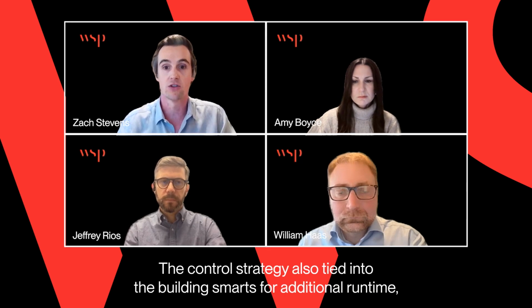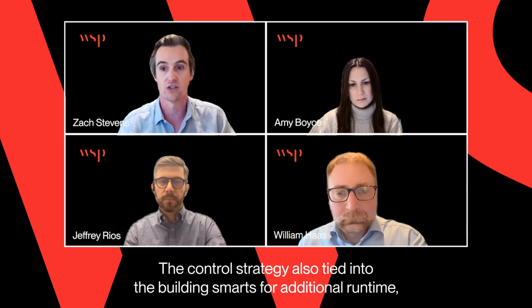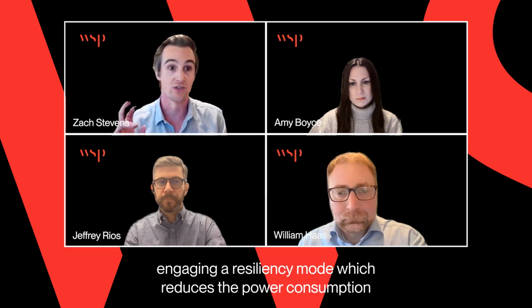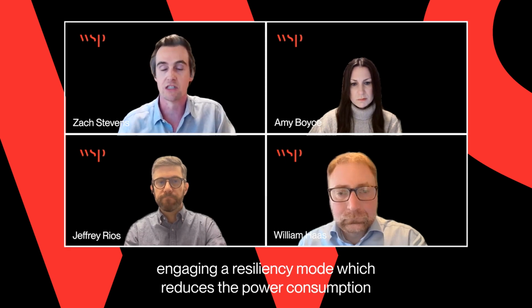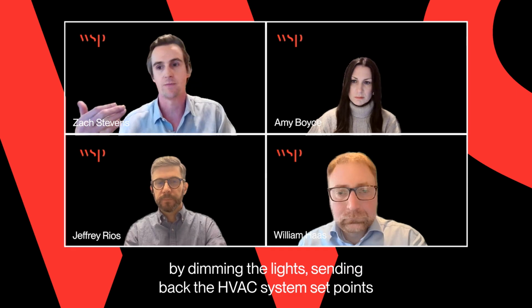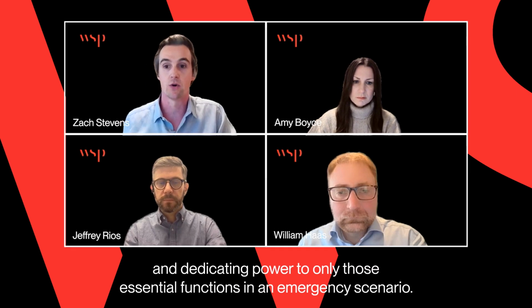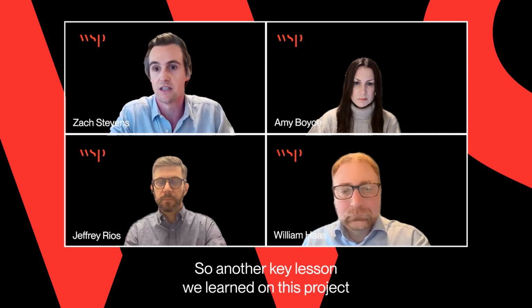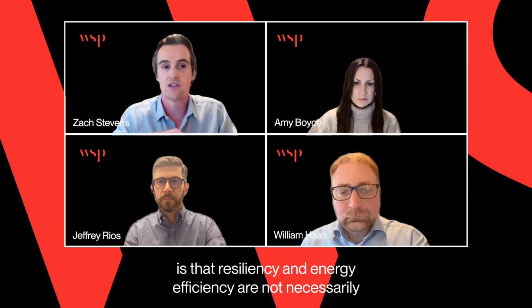The control strategy also tied into the building smarts for additional runtime, engaging a resiliency mode, which reduces power consumption by dimming the lights, setting back the HVAC system set points, and dedicating power to only those essential functions in an emergency scenario. So another key lesson we learned on this project is that resiliency and energy efficiency are not necessarily competing interests on a project with a fixed budget.